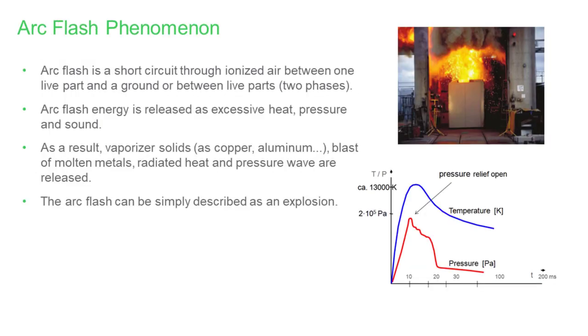Thank you, everyone, for joining this presentation. Today we will focus on arc flash protection — how we apply it and what we call the arc flash. At the beginning, let's look at some basics. The arc flash is a short circuit through ionized gas; it could happen between phase-to-ground or phase-to-phase. There is extensive energy released during the arc flash: high pressure, heat, and sound waves. There will also be vaporized solid material like copper or aluminum, globs of molten metal, and radiant heat. Because of the nature of this phenomenon, we can categorize it as an electrical explosion.